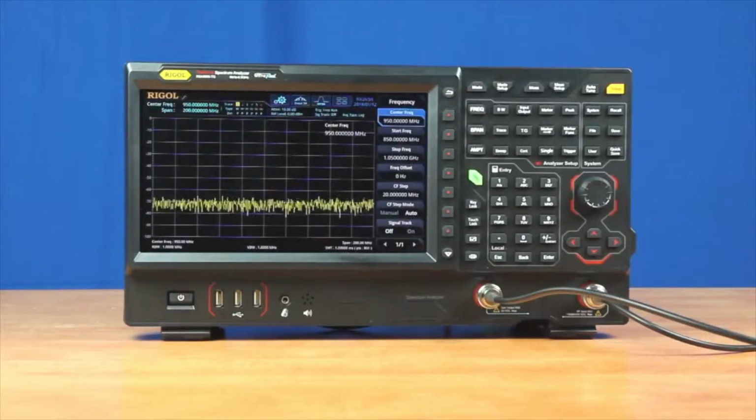By adding a tracking generator, or TG, option to the RSA 5000, your instrument will be able to perform antenna testing, cable normalization, VSWR testing, and filter testing. The tracking generator is used in the general purpose mode and is either used to sweep a frequency range at the same rate as the RF input, or at a fixed frequency when the instrument is set to zero span mode.